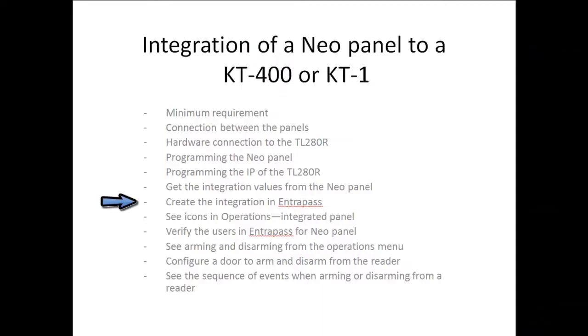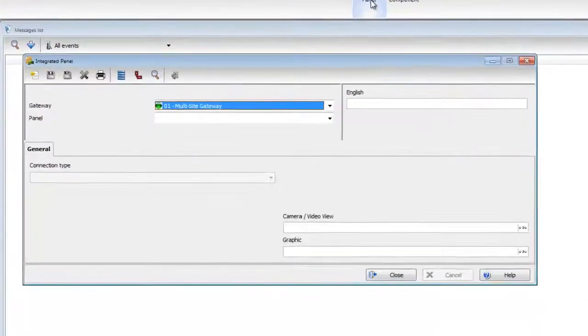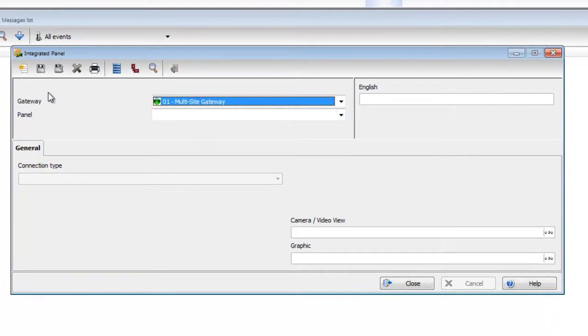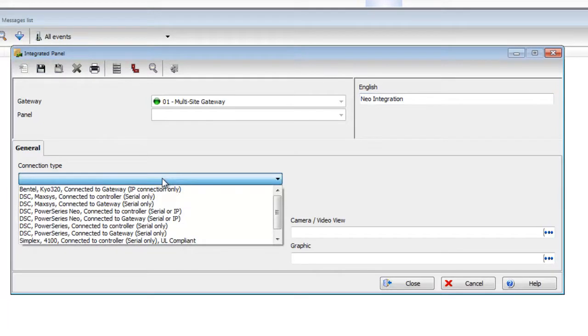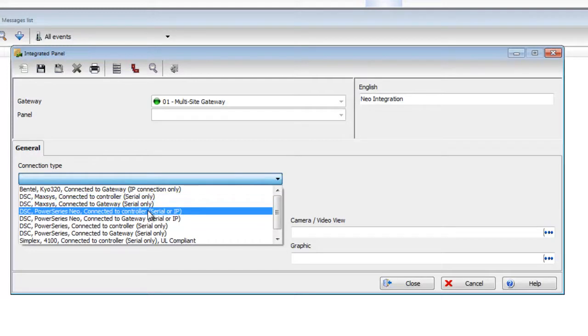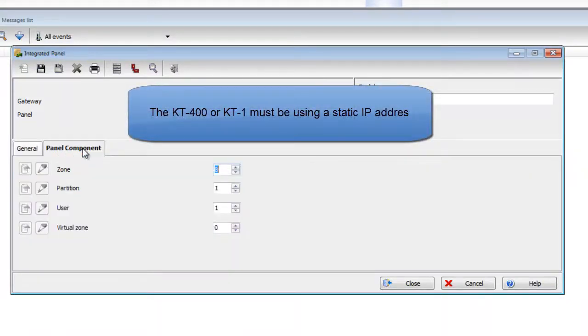Now let's go ahead and create the integration in the EntraPass software. We'll want to go to Devices, Integrated Panel, and click the New button to create a new integration. Let's call this Neo integration. For connection type, we're going to select DSC Power Series Neo, connect it to a controller, serial or IP — in our case it's going to be IP. Remember that the KT400 or KT1 must be using a static IP address for this.